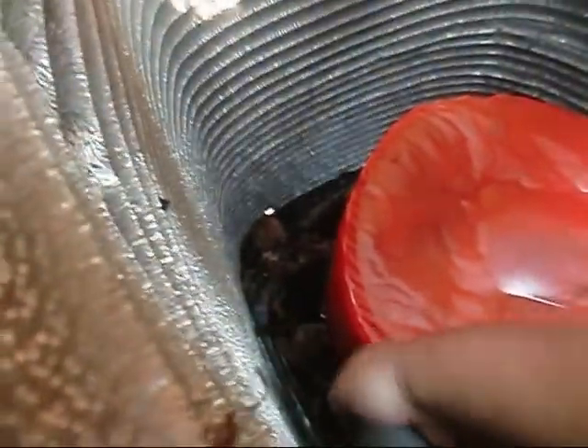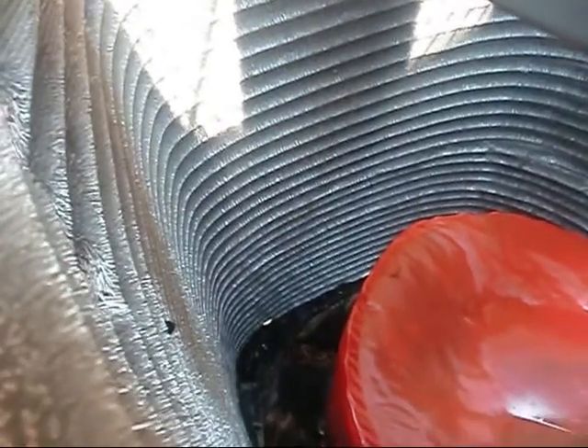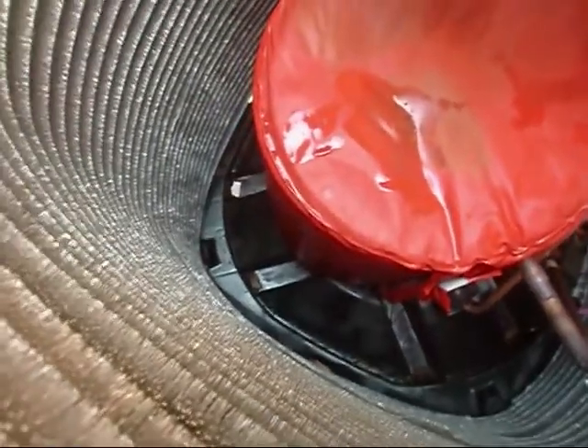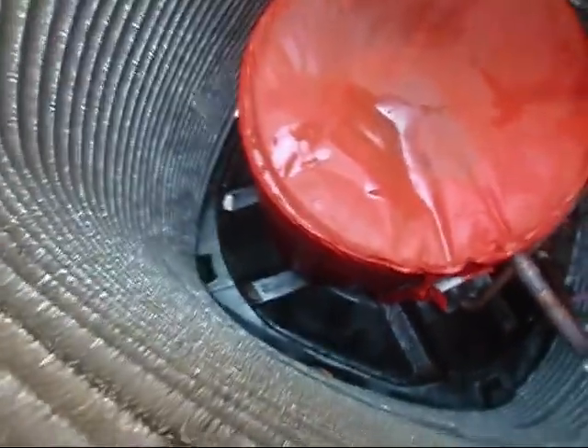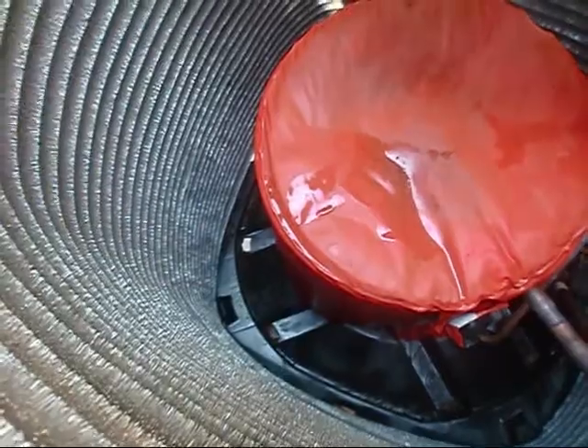I know this is probably overkill, but we have to have our heat pumps on snow legs here in our state — I'm sure it's probably like that in every other state too. As you can see these drain holes, I want them to be able to drain. So we'll just take our time and get your leaves out. You can see right here where I'm pointing with my wand — you can actually see the holes. These composite plastic bottoms in these units — I'm really glad they went to these, because if somebody were to leave those leaves in there and nobody stayed up with their maintenance, I'd say within three years that bottom's going to be rotted out.